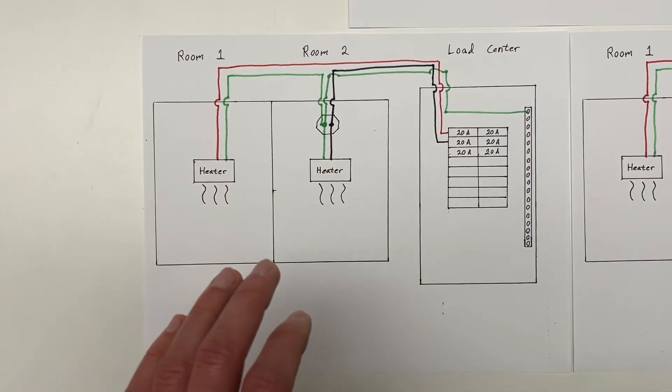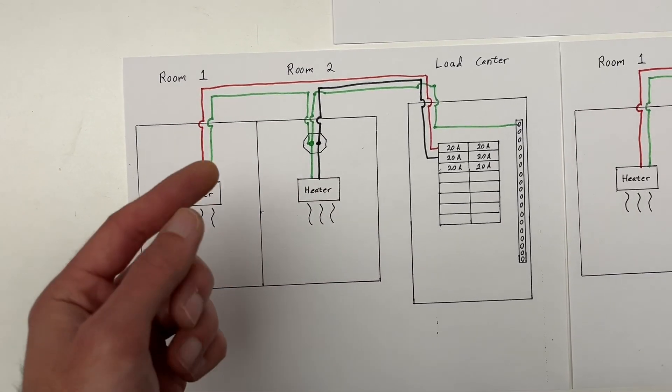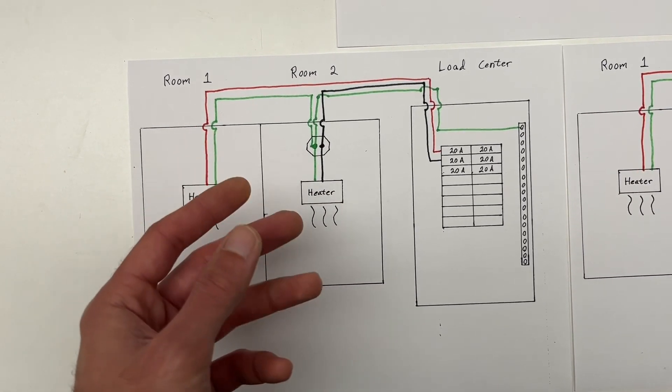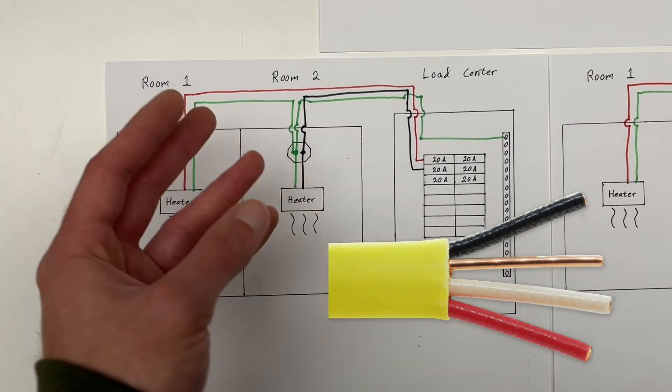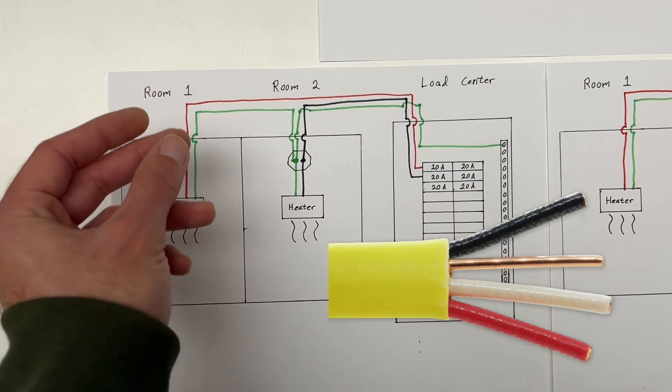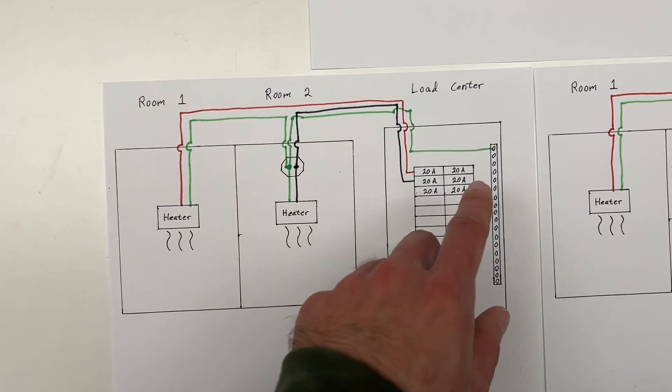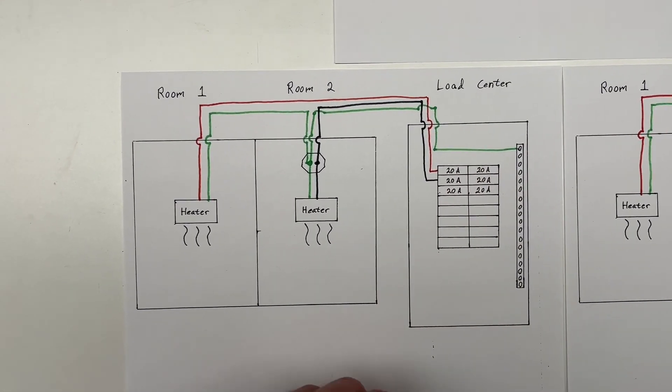Here is how several of the circuits in my house are wired up. It uses three conductor wire. So instead of just black and white and ground, you have red, black, white and ground. In my drawings here, I'm showing white and ground as just green because ultimately they're bonded back at the panel somewhere.